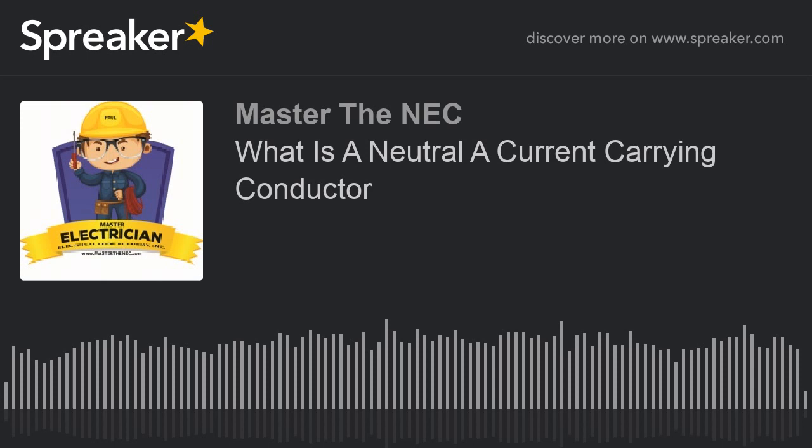So let's look at A. In A, again, we're talking neutral conductor. It says a neutral conductor that carries only the unbalanced current from other conductors of the same circuit shall not be required to be counted when applying the provisions of 310.15(B)(3)(a). All right, pretty straightforward there, right?